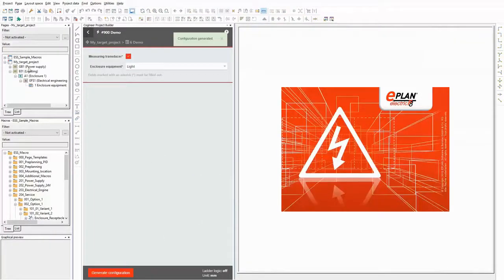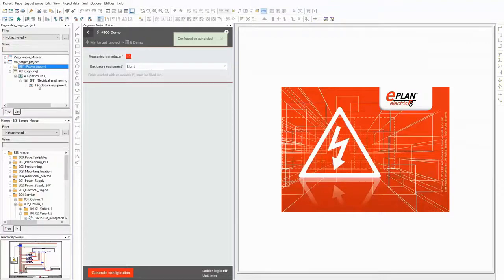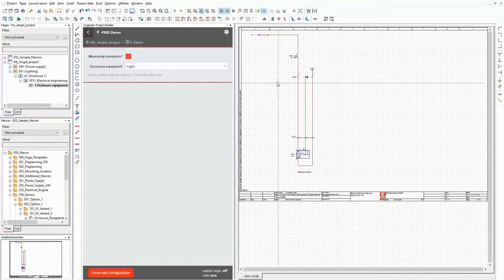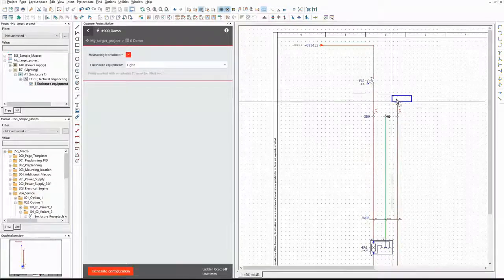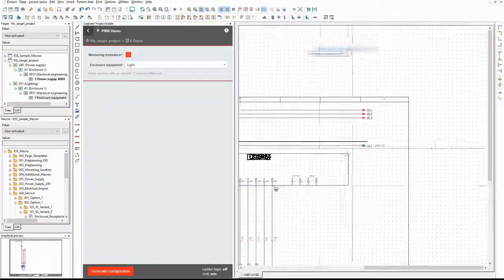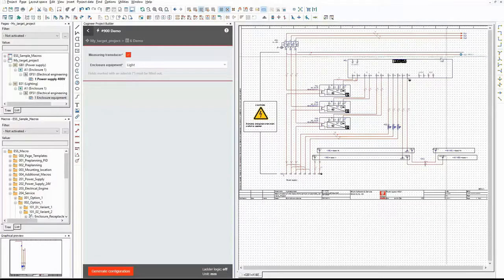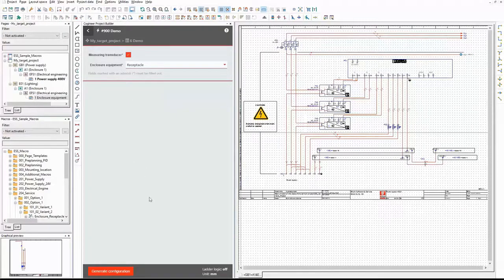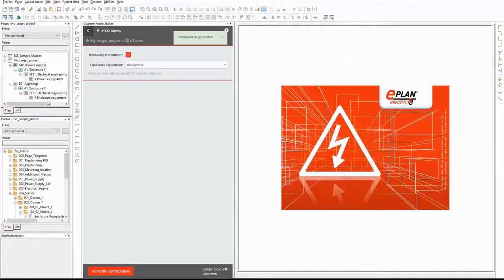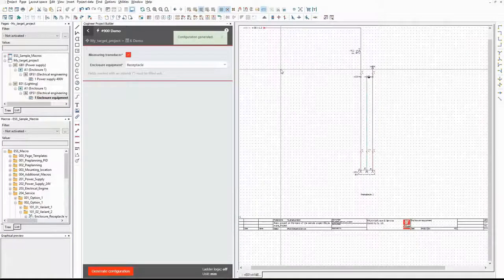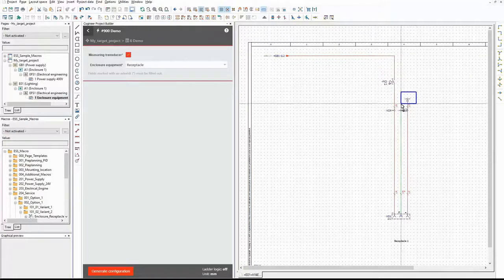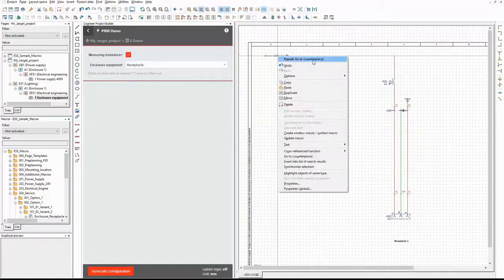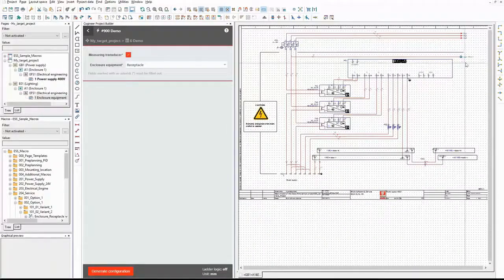Let's select the option light and generate the next variant. There is a new page in the target project, and there is the enclosure light. The values that I have entered in the designer for this macro are used for the circuit breaker and the bus bar. And on the power supply page, only one of the single wires is used. Let's switch to the option receptacle and see what happens. There it is. As you can see, the same values are used for the circuit breaker and the bus bar, because there is no light in the enclosure. And on the other page the other single wire is used. That's correct too.